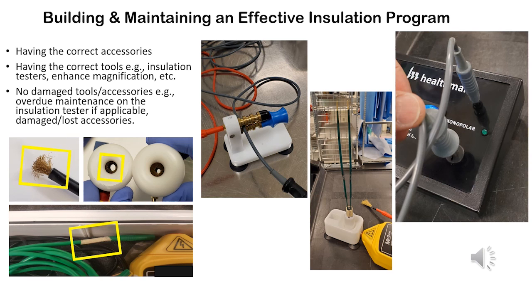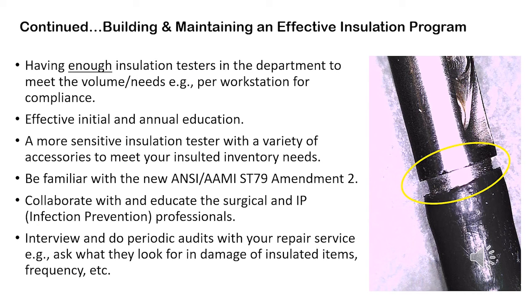To continue with that, having enough insulation testers in your department, having them per workstation, or if you have 4 workstations, but really you only use 2 of the workstations to do insulation trays, then you would need 2. You also want to have effective initial and annual education, not just initial, where maybe you forget in over a year, or maybe you weren't even there for that specific initial education, and you want to have an ongoing one annually. A more sensitive insulation tester with a variety of accessories to meet your insulation inventory needs.